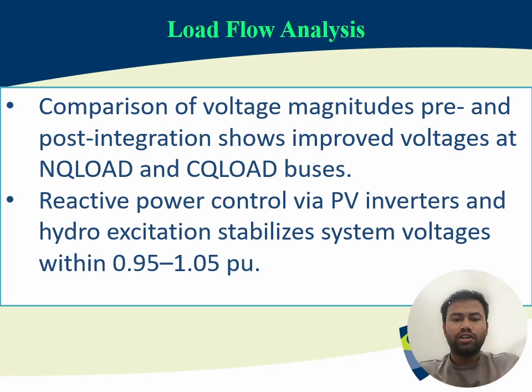I will now cover the results of our load flow analysis. In short, the analysis confirmed two key successes. First, we have seen a clear improvement in voltage magnitudes at the NQ load and CQ load buses. Secondly, by using reactive power control from the PV inverter and hydro excitation system, we have successfully stabilized all system voltages within the target range of 0.95 to 1.05. This directly enhances grid reliability and power quality.